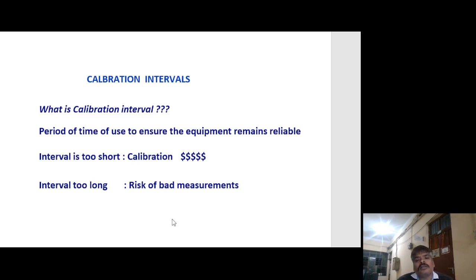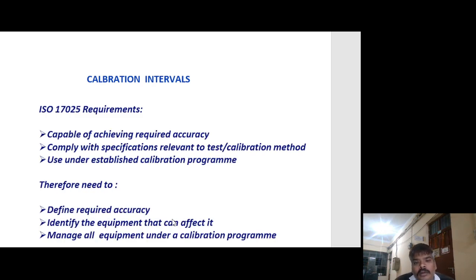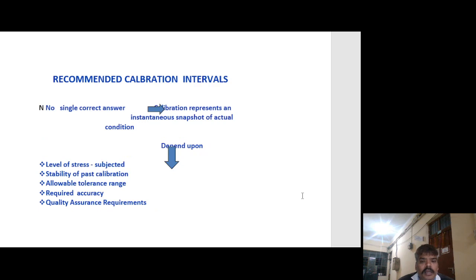If the calibration interval is very short, calibration cost will be very high. If too long, there is a risk of bad measurement. The period of time of use must ensure equipment remains reliable. ISO 17025 requirements for calibration interval state that equipment must be capable of achieving required accuracy, comply with specifications relevant to the test or calibration method, and be used under an established calibration program. Therefore, you need to define required accuracy, identify the equipment that can affect it, manage all equipment under a calibration program, and recommend calibration intervals.